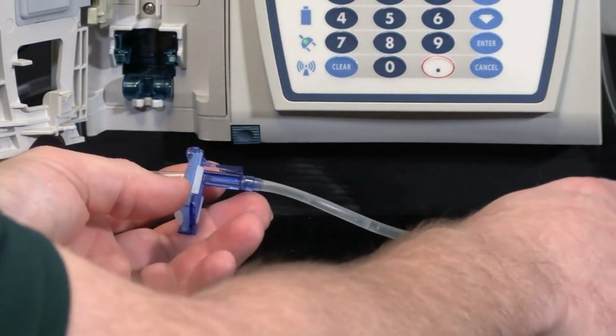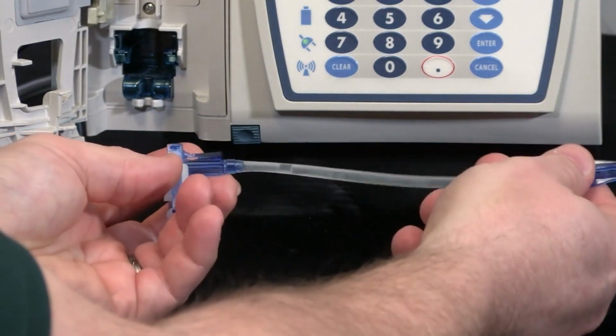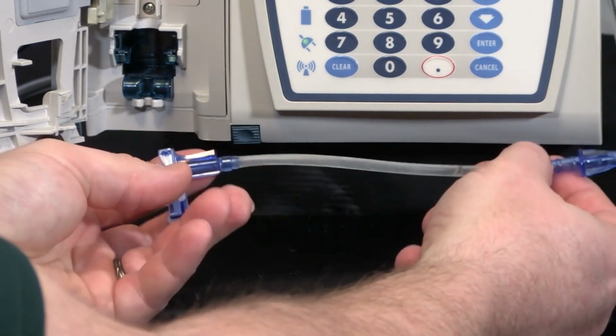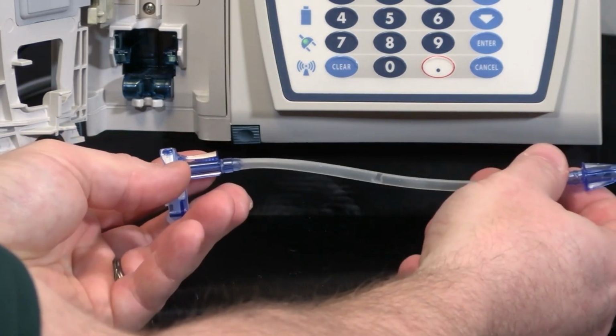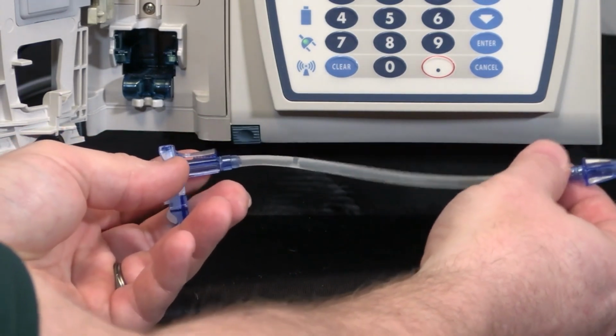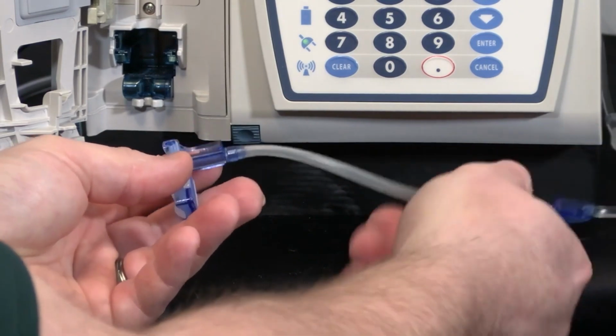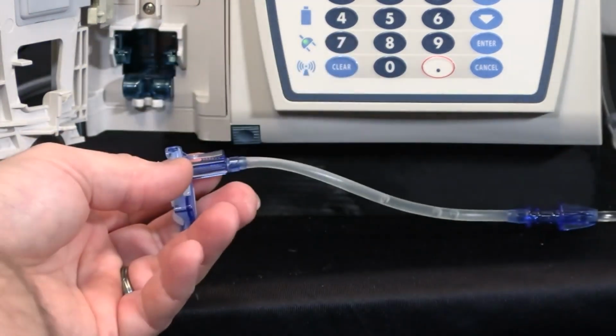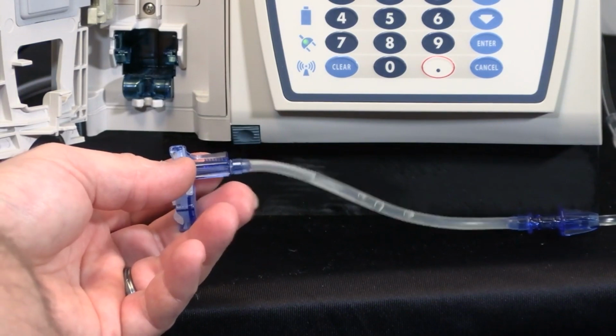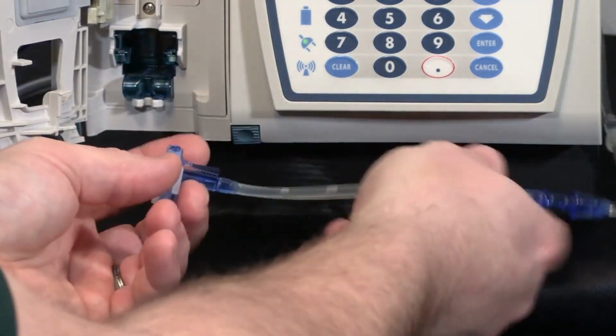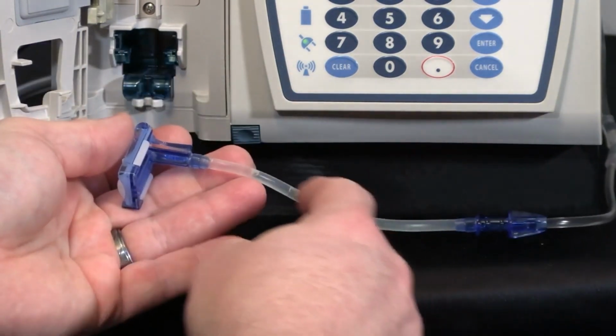Now we can see the fluid passing through the tubing here. And we know if we leave any of these bubbles in there, the pump is going to complain, it's going to cancel the test, it's going to have lots of problems. So what we can do is just leave the infusion pump analyzer in the drain mode, and it's going to continue to pump all of these bubbles out.